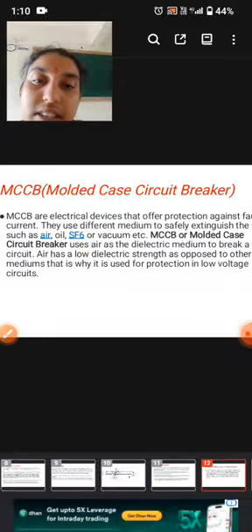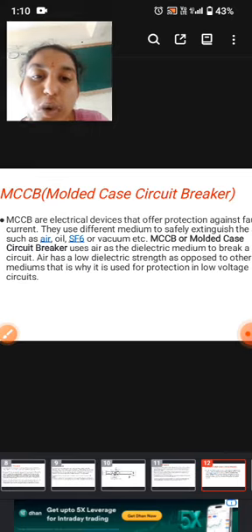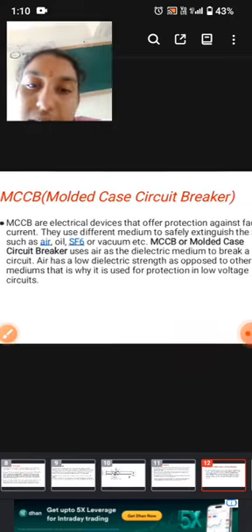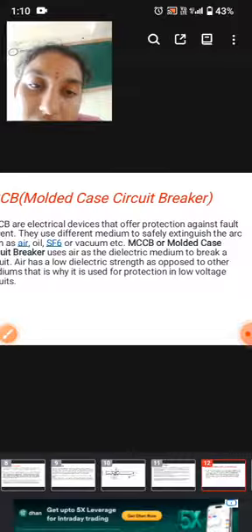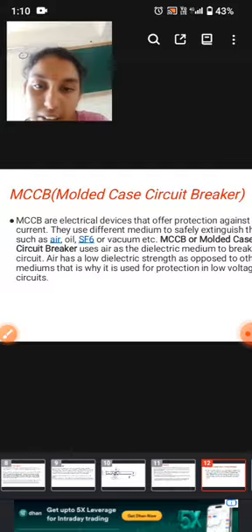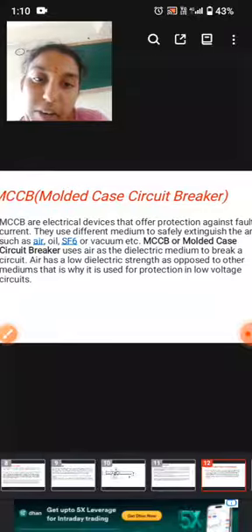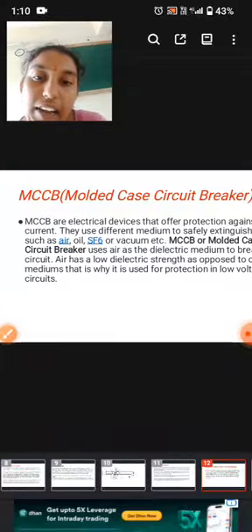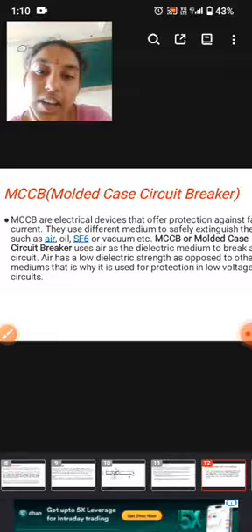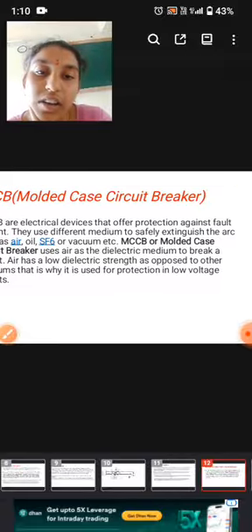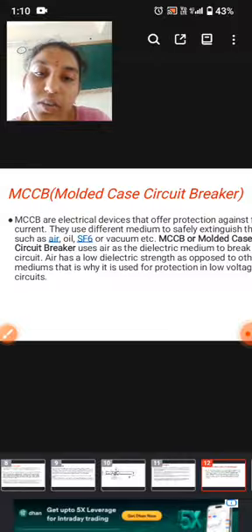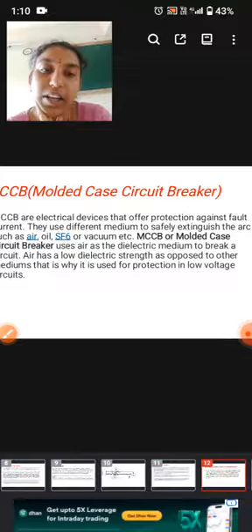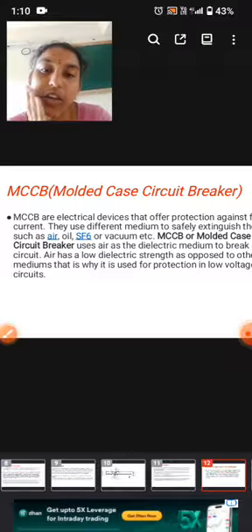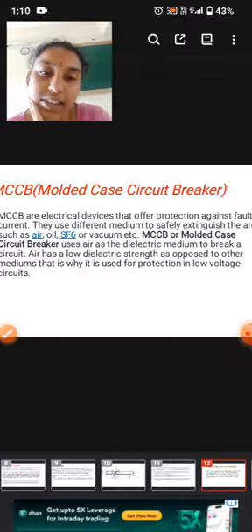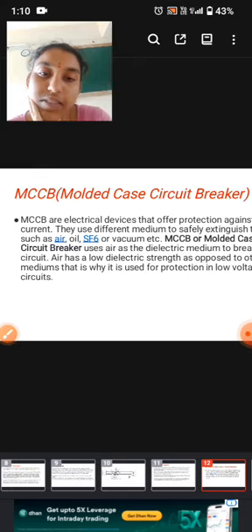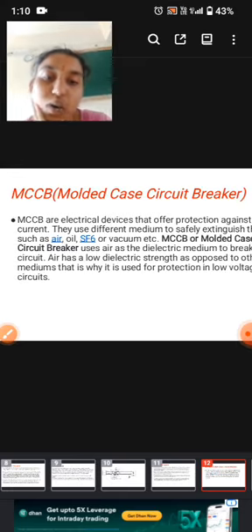Now we'll look at MCCB. The full form of MCCB is molded case circuit breaker. MCCBs are electrical devices that offer protection against fault current. They use different media to safely extinguish the arc, such as air, oil, SF6 or vacuum. MCCB, or molded case circuit breaker, uses air as the dielectric medium to break a circuit. Air has a low dielectric strength as opposed to other media. That is why it is used for protection in low voltage circuits.